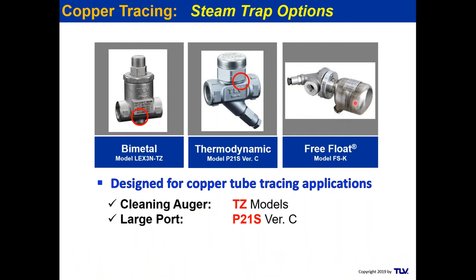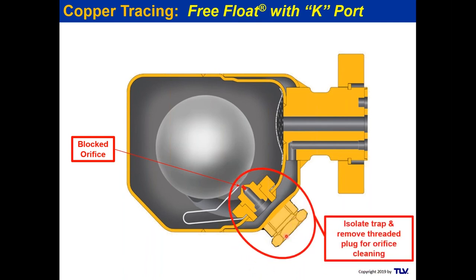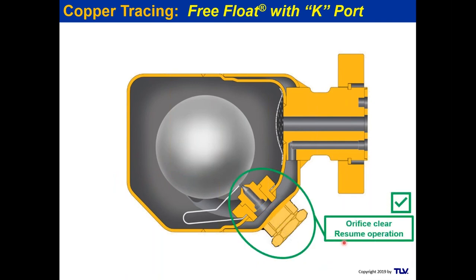For critical heating processes requiring near-steam-temperature discharge, a free float mechanical steam trap with a K4 clean-out port is available. The K port — located at the back of the trap at the orifice — can be threaded out to provide access. A welding rod or clean-out rod can then clear blocked debris, restoring a clear flow path and resuming normal reliable operation without full trap replacement.